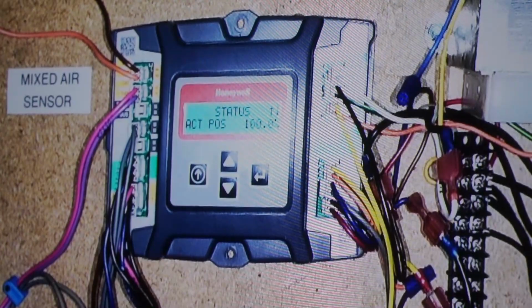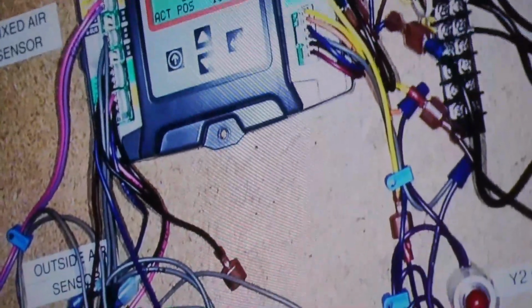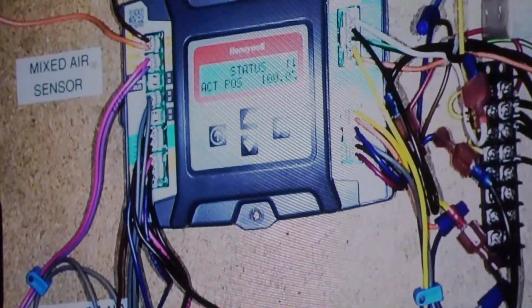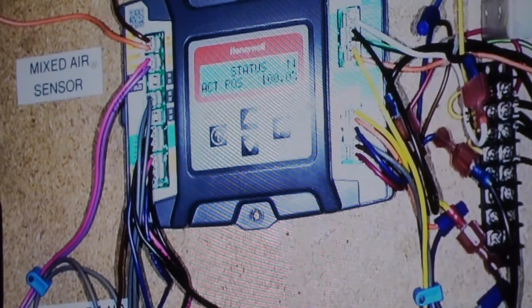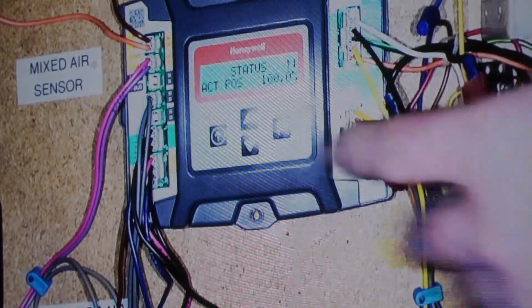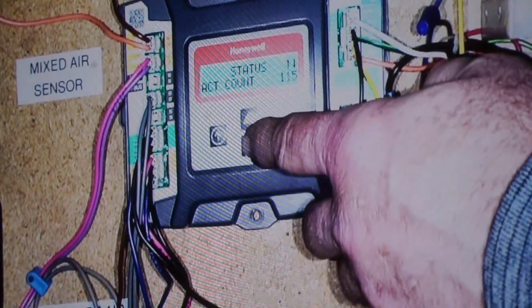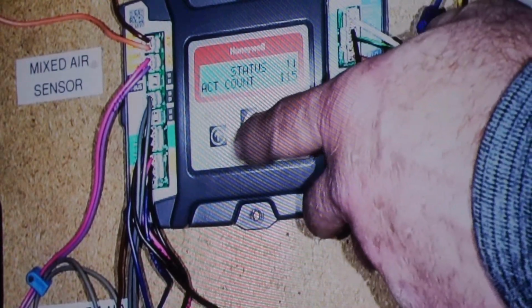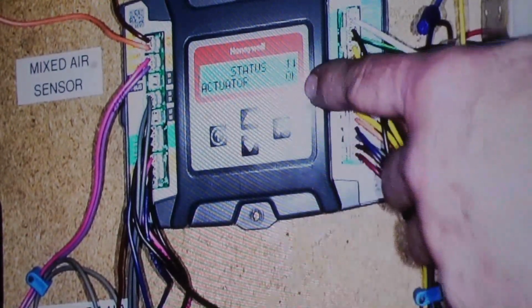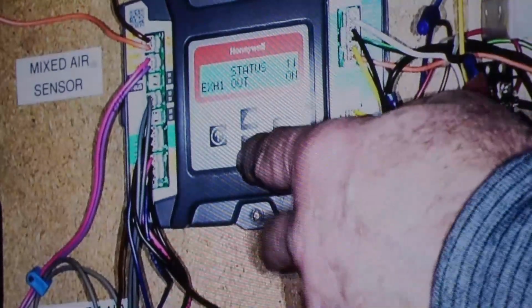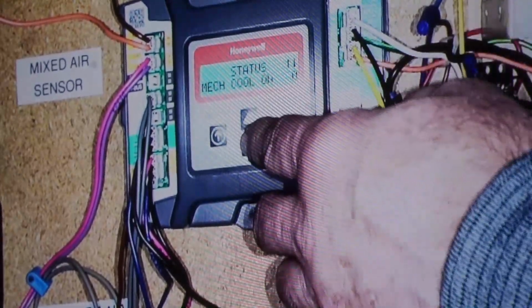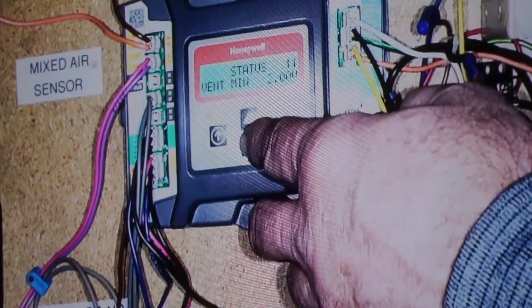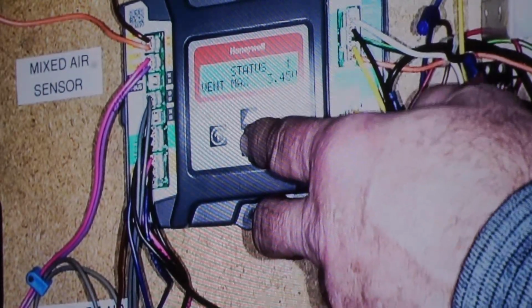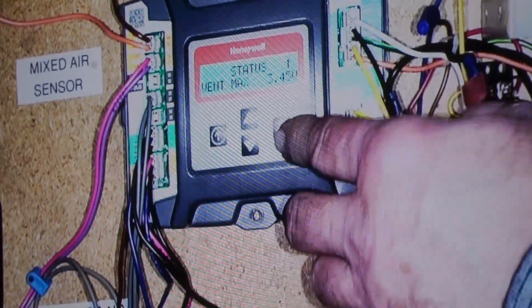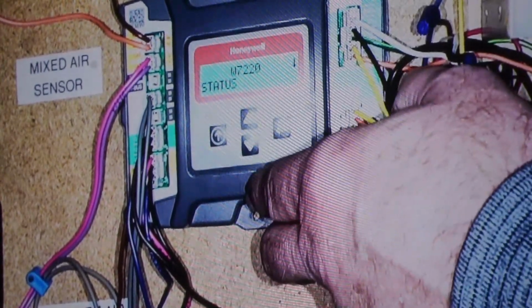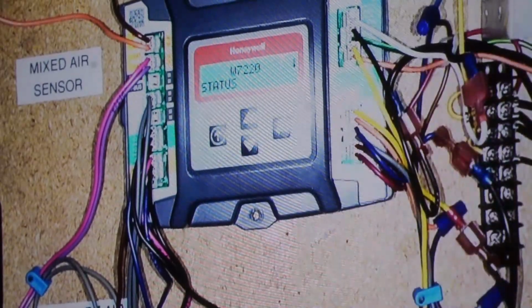My exhaust is now on. There. Because of my dampers, quite a bit open. And then my actual counts, that's going to tell you how many full open-close strokes that damper's had, and my actuator checks out okay. That's the end of that menu. Oh, my exhaust status is on. That's the end of it. Better tighten some terminals real quick. Yeah. So, exhaust status was on.